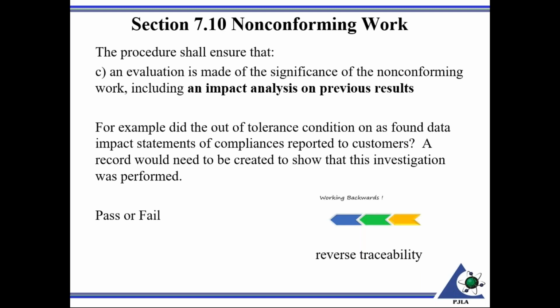So basically, go back, look at those pass-fail statements. This often implies something called reverse traceability, where you basically have to go back, look at the specific, in the case of the as found failures, the instrument that was out of calibration, and see basically what it was used for since the last time it was determined to be within tolerance.